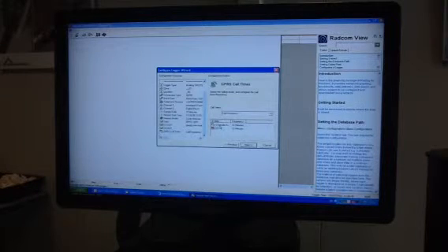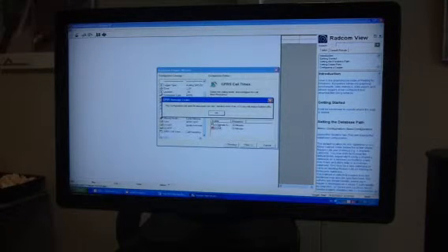If you're going to use 15-minute data, you need to have a battery pack connected. If you haven't got a battery pack connected, you can only have up to 3 call-ins per day. Once you've selected that, click next, and then it just gives you a warning. This configuration will send so many messages per day and it will reduce your battery life. So press OK.